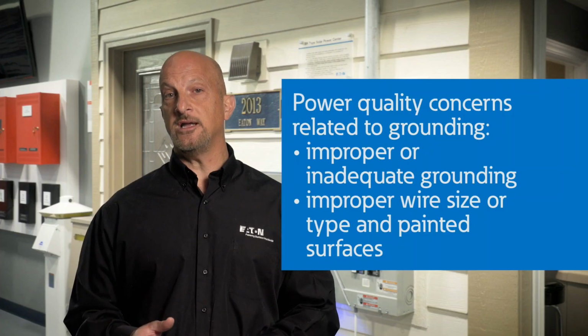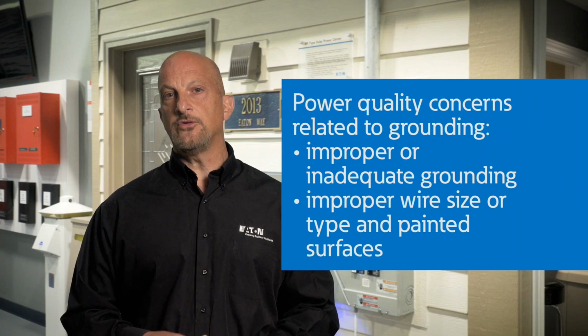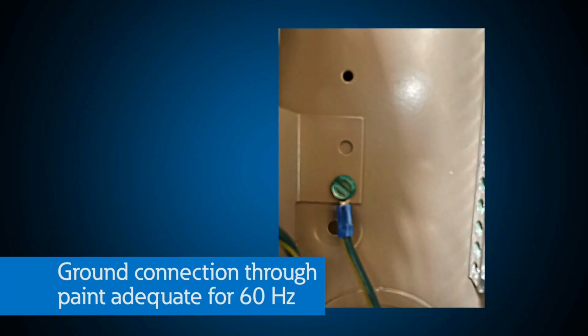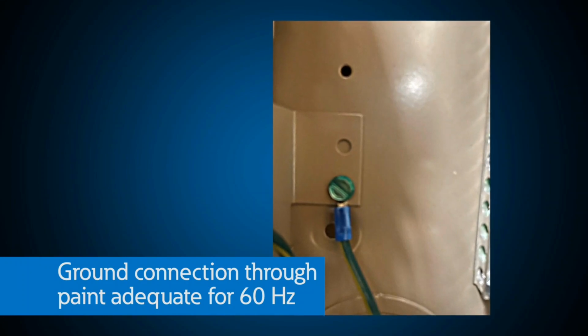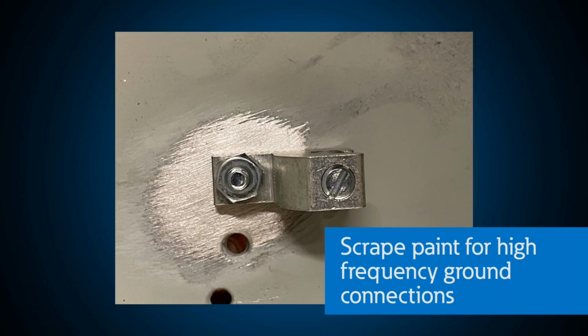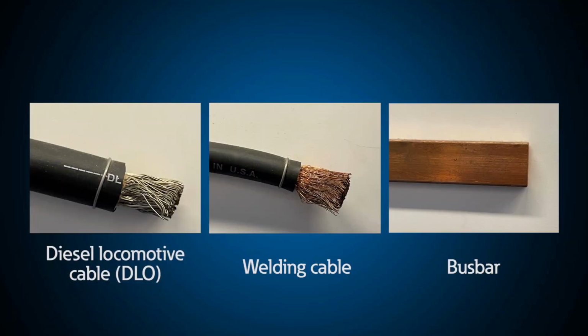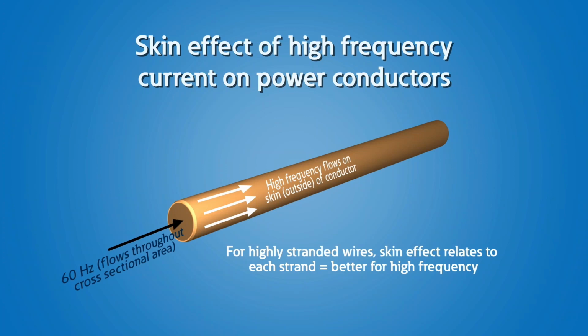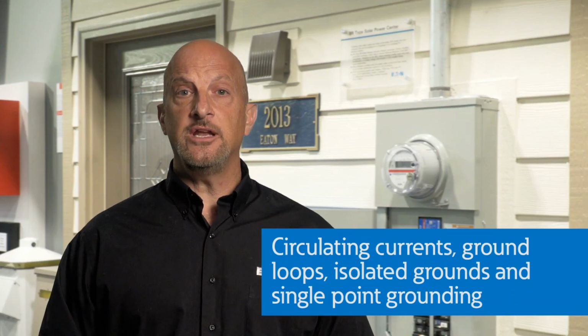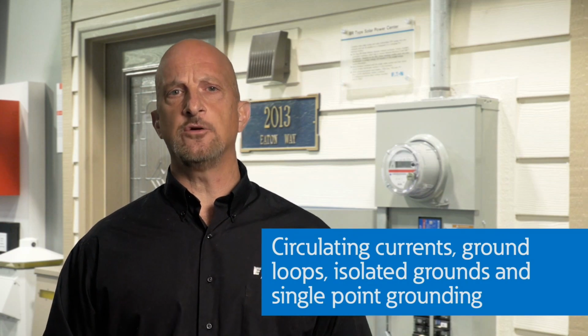Improper wire size or type and painted surfaces. For example, 60 Hz currents will generally penetrate painted surfaces during fault conditions, but oftentimes higher frequency currents may or may not be adequate to provide a low impedance path for stray or unwanted currents from electronic components or induced currents from PWM inverters. In most cases, highly stranded and braided cable or bus bar with the shortest possible length is the most appropriate grounding method for high frequency currents, as it provides significant surface area for the skin effect phenomena of high frequency currents. Circulating currents, ground loops, isolated grounds, and single point grounding.